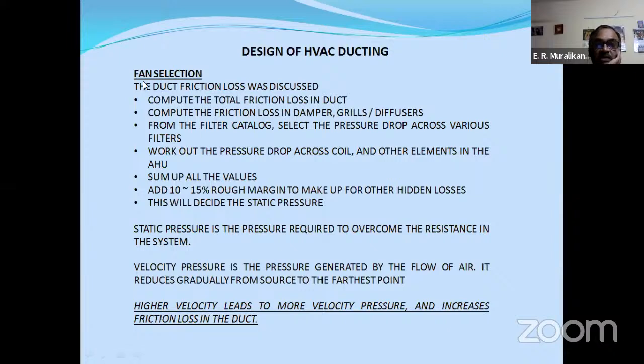The fan selection. We already discussed the friction loss. Compute the total friction loss in the duct. Compute the friction loss in dampers, grills, diffusers. From the filter catalog, select the pressure drop across various filters. Work out the pressure drop across the coil and other elements in the AHU like the heating coil, cooling coil, and UV lamp or whatever it is. Sum up all the values. Roughly 10 to 15% we take for the hidden losses, like branches, the T joints, and some unknown barriers coming in the systems.